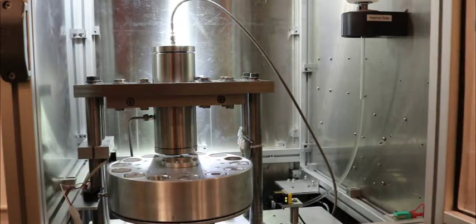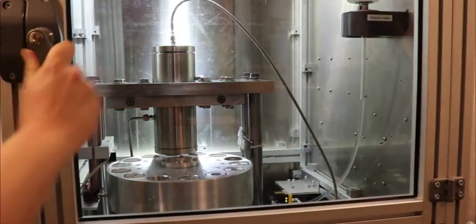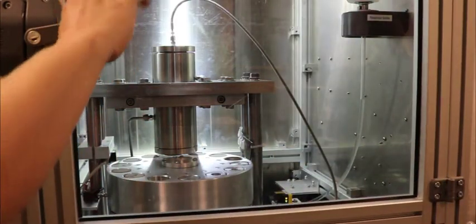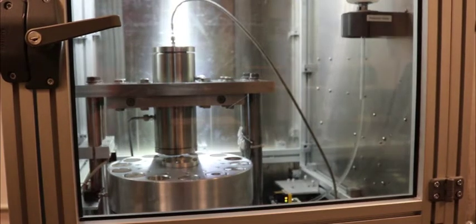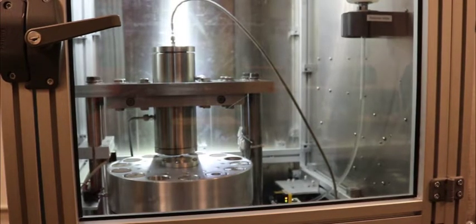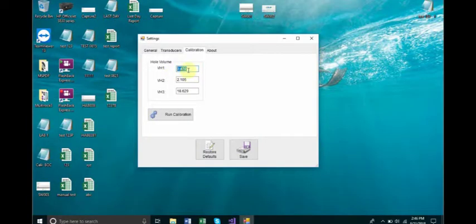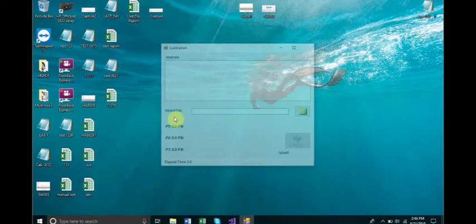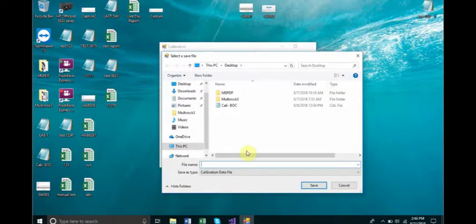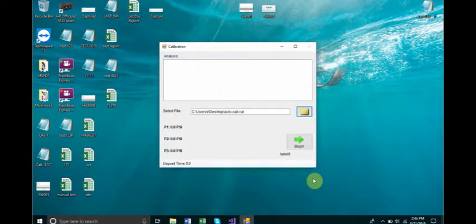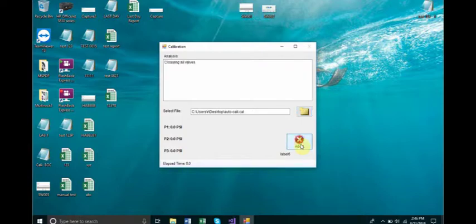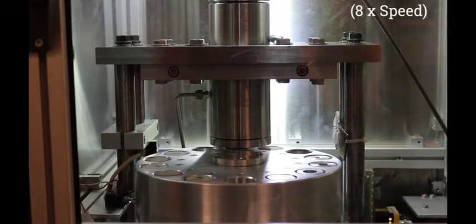The PMI APDP-HP101 has a safety feature which prevents components from operating unless the doors are closed. Please make sure they are closed before operating the machine. Once you have entered the values for calibration plug volume into their respective fields, click run calibration. Then choose a name and path for the file that will be created by the calibration sequence. Click begin, and the automatic calibration sequence will start. It should take approximately three hours to complete.